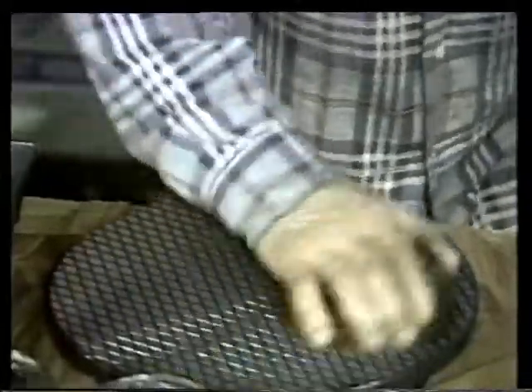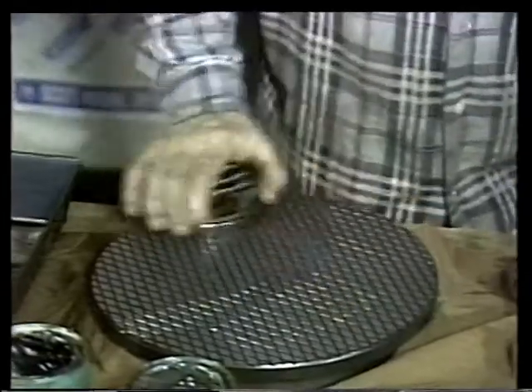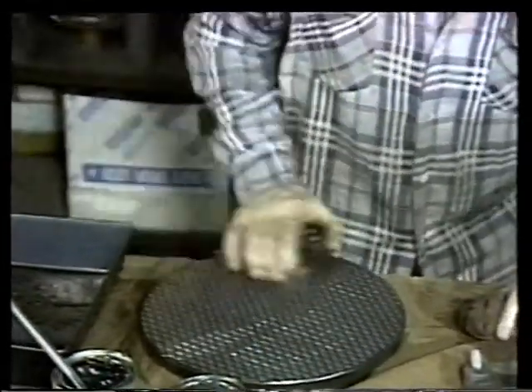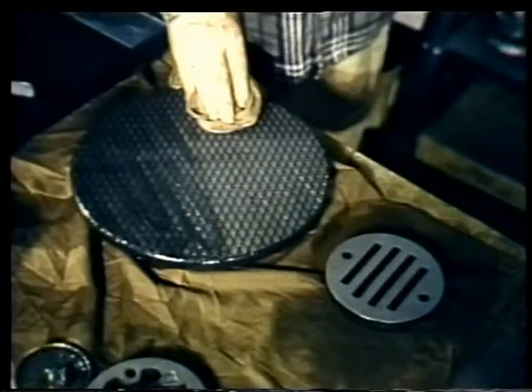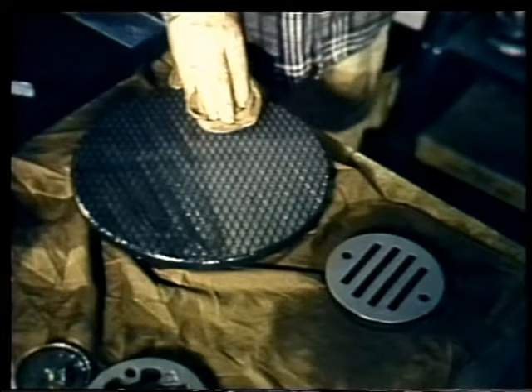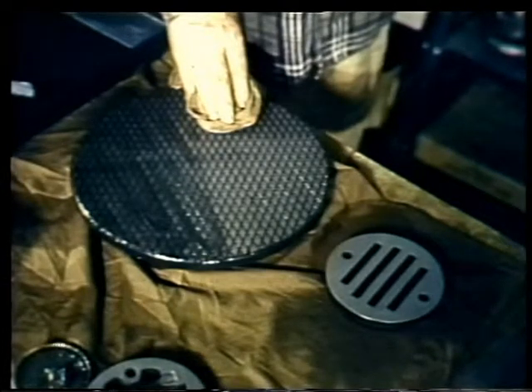Lapping is done by applying a thin coat of lapping compound to a lapping block. Then you place the valve seating surface down and apply light pressure using a figure eight motion. After cleaning the lapping block, this procedure is repeated using progressively finer grades of lapping compound until you've got the right finish. Then all traces of lapping compound must be removed. Otherwise, it will interfere with the next process, bluing.